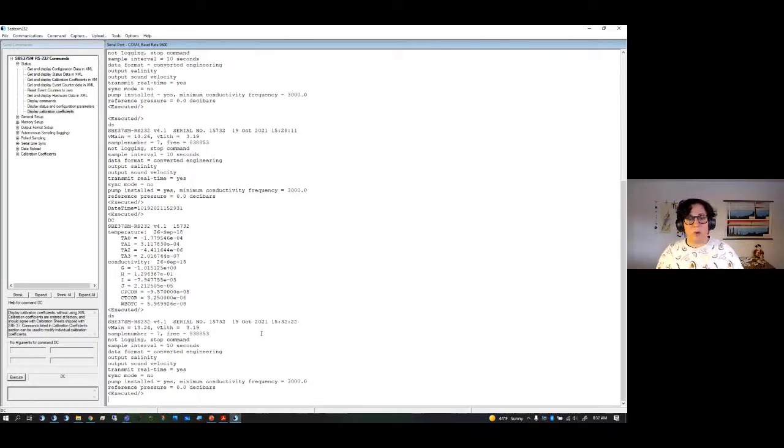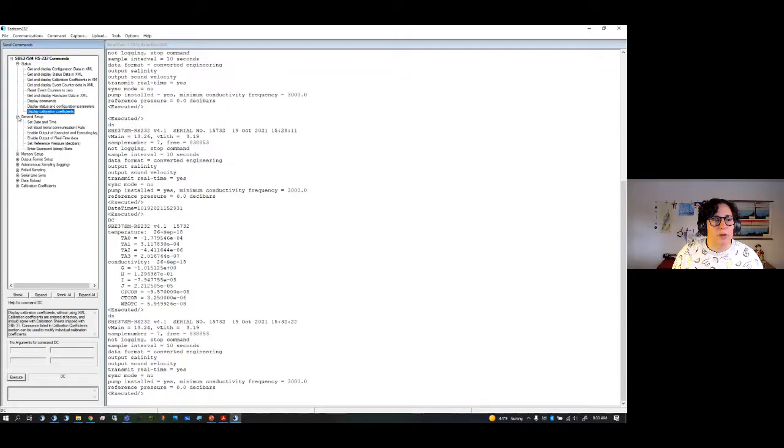If I was doing it in freshwater, you don't have such a big change in conductivity. It would be what you see on your calibration sheet plus 5. And you can do this here in general. Sorry, I have to find the actual one.